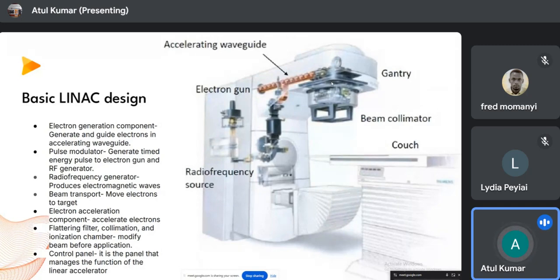If you don't want X-rays, if you want electrons only, you can get electrons directly outside. If you want X-rays, you have to make the electrons hit a target. That target is usually a very high atomic number material, maybe tungsten, and then you get your Bremsstrahlung X-rays. We will discuss the physics of the production of X-rays. And then you collimate that X-ray. How do you collimate? You use the primary collimator, then the JAWS secondary collimators. Then you can also use MLCs and several other techniques of MLC movement, like IMRT or VMAT. Then we can collimate those X-rays to target the tissue that we want to treat.